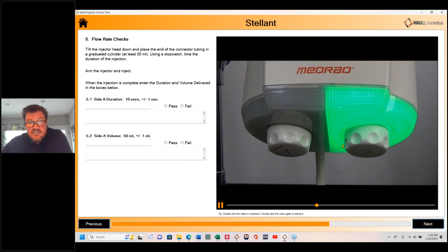And then this just goes through. Now, this is not critical. The timing is not critical. We don't need an electronic timer here, so just a standard stopwatch will do. We're going to start and stop the stopwatch with the start and stop of the injection. It's 50 milliliters, plus or minus 1, and 10 seconds, plus or minus 1 second. And over here, as I mentioned earlier, I can't just hit pass, because these boxes are asking for a specific time and volume. If you click next, it says please answer everything on the screen and continue. So we're looking for 10 seconds and a volume of 50 milliliters plus or minus 1. We'll put 50 and 10 and 49 here.